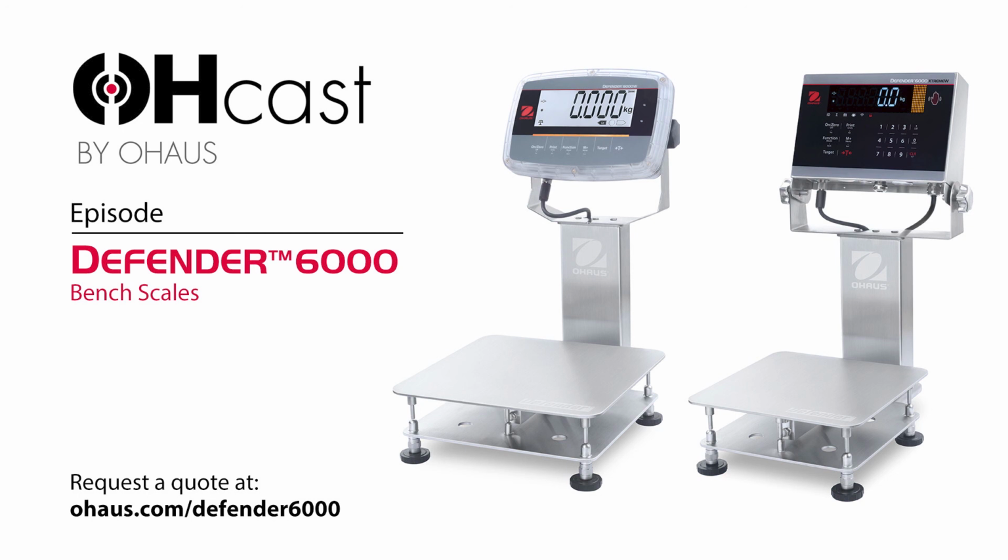We also were responding to requests for different variations in the bases. So in our older generation, we only had about 17 bases. We now have increased that to 34 because within each size, there could be different situations where a customer may want to have a 12-inch square platform. One customer wants, let's say, 25 pounds. The next customer wants 50 pounds, and they are using a lower resolution. So really the idea was to give more options for our dealers and for end users to use our Defender series with their operations. That's great.